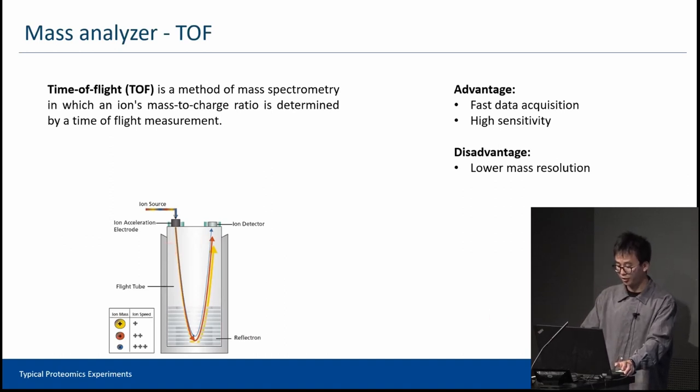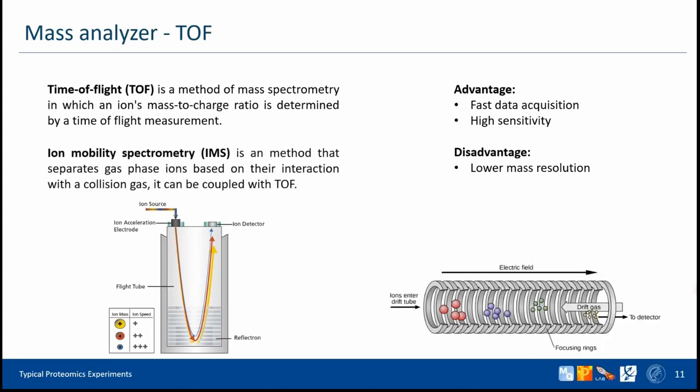In recent years, it's very popular to couple ion mobility spectrometry together with TOF to add an extra step to separate molecules, like Timstof. Here, ions are propelled through a tunnel by gas flow. At the same time, an electrical field controls each ion from moving beyond a position defined by ion mobility, where the push from gas flow matches the force of the electrical field. Ramping down the electrical field allows selectively releasing ions from the tunnel according to their mobility. This extra separation works very well.